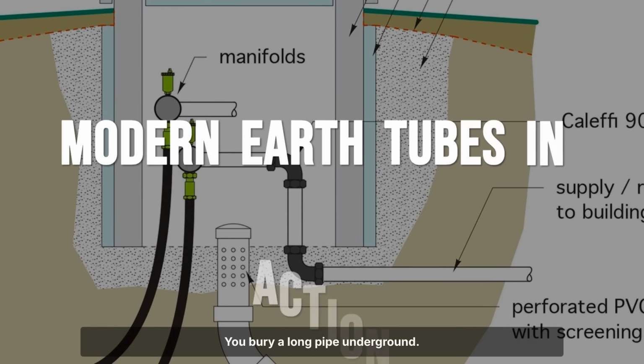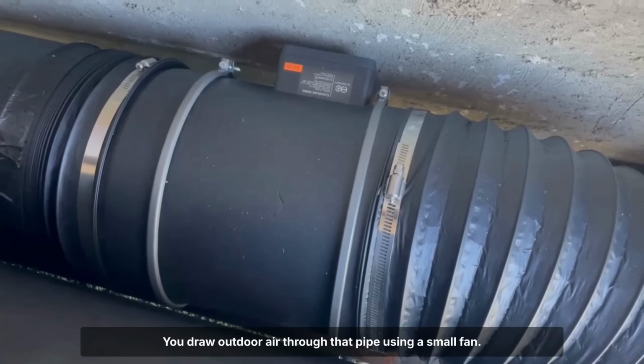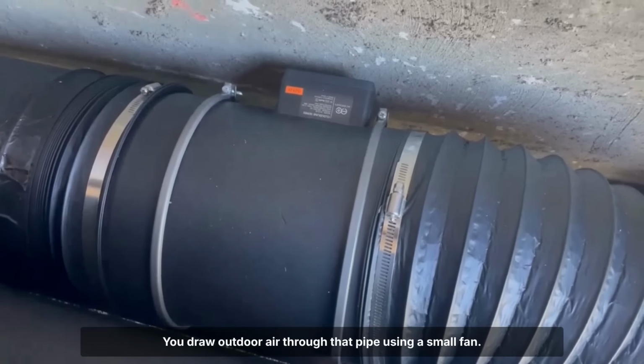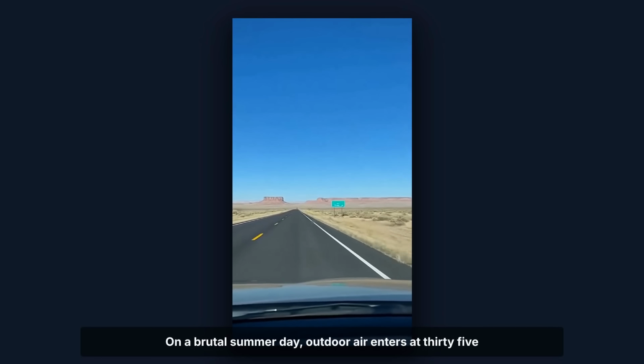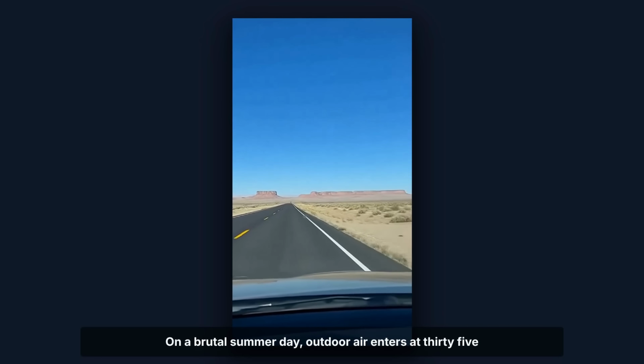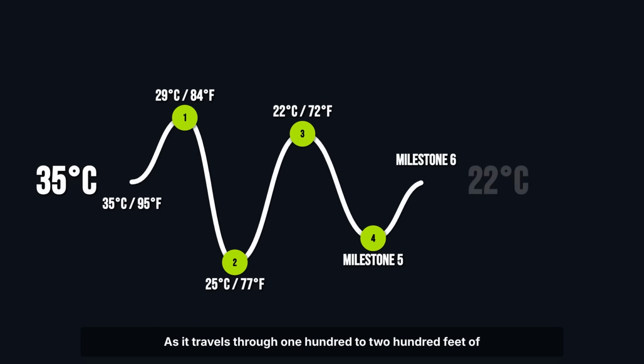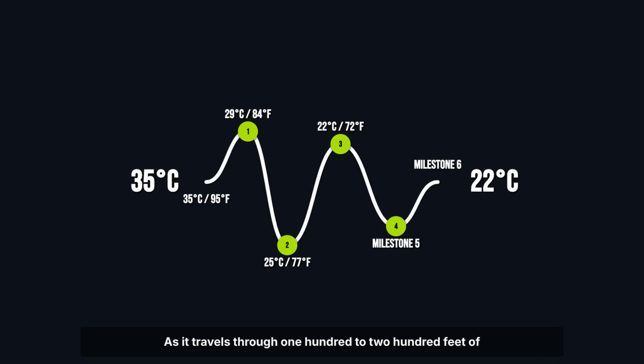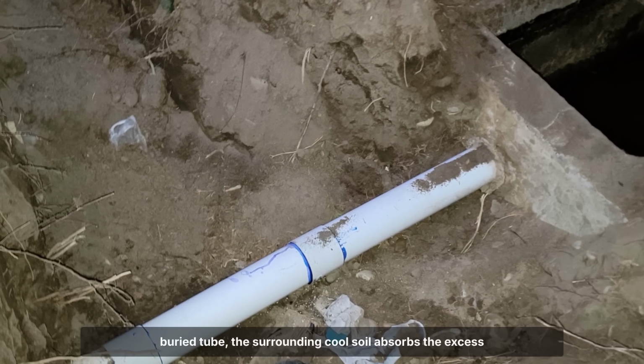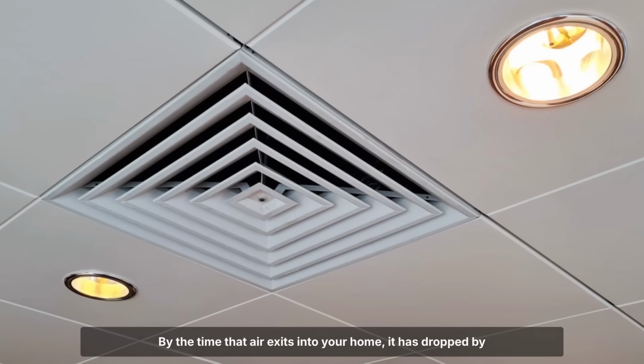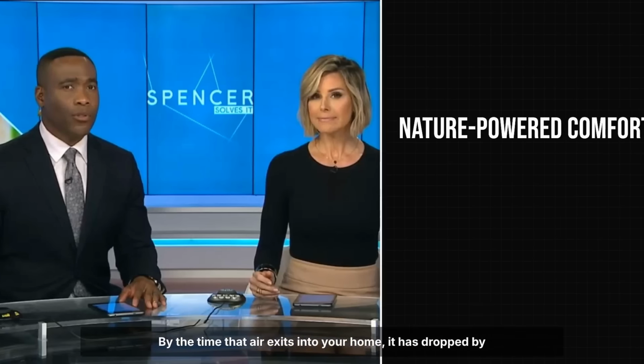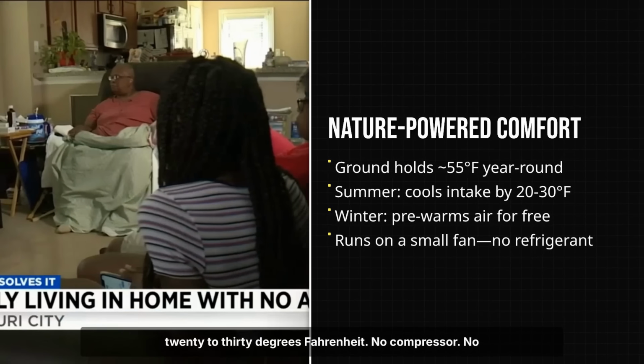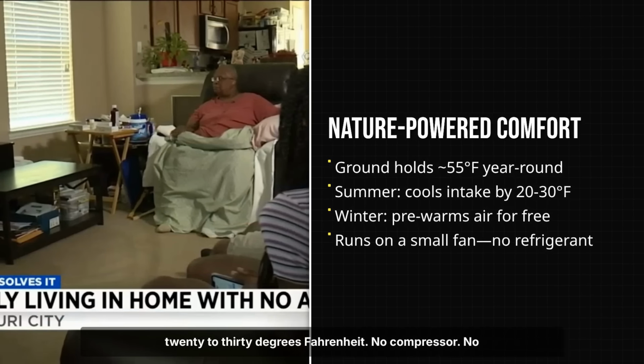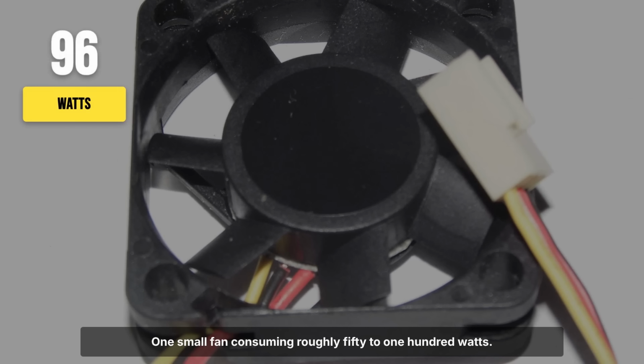You bury a long pipe underground. You draw outdoor air through that pipe using a small fan. On a brutal summer day, outdoor air enters at 35 degrees Celsius. As it travels through 100 to 200 feet of buried tube, the surrounding cool soil absorbs the excess heat. By the time that air exits into your home, it has dropped by 20 to 30 degrees Fahrenheit. No compressor, no chemical refrigerant. One small fan consuming roughly 50 to 100 watts.